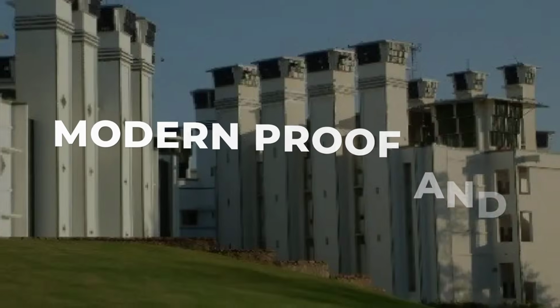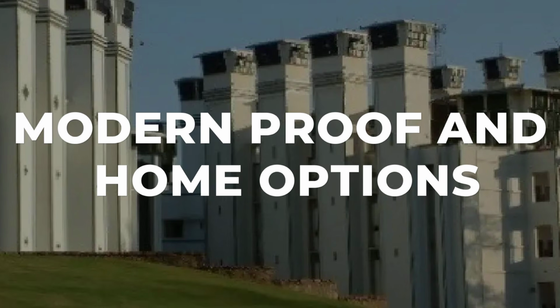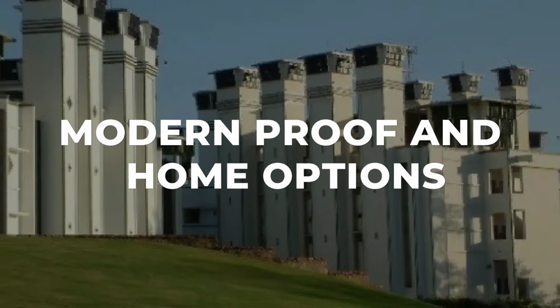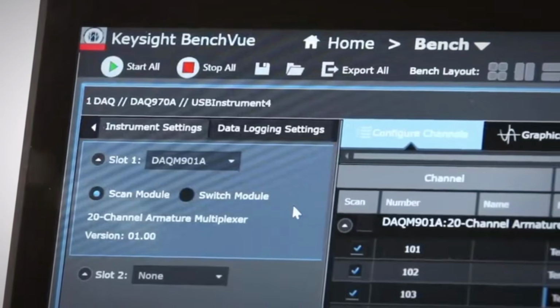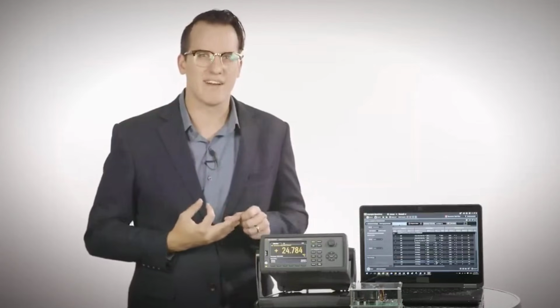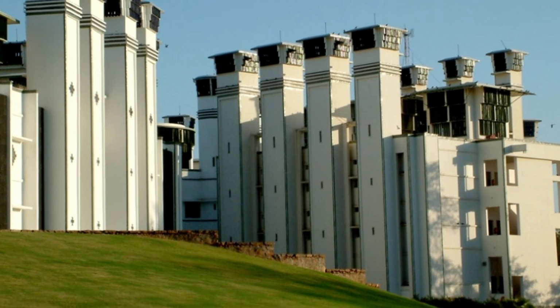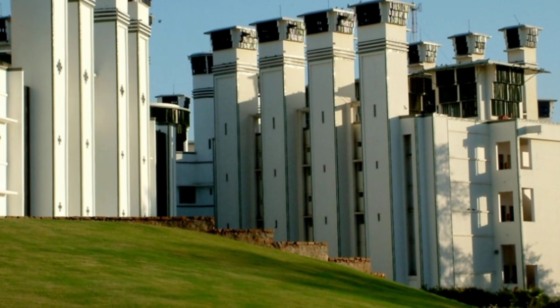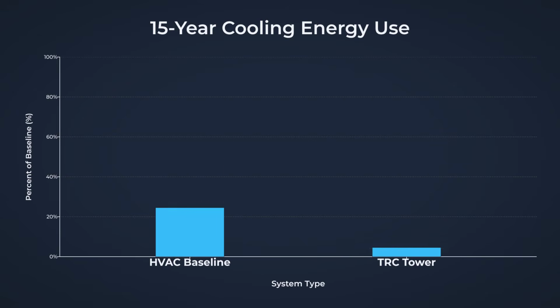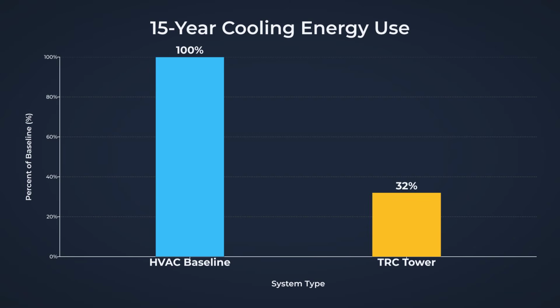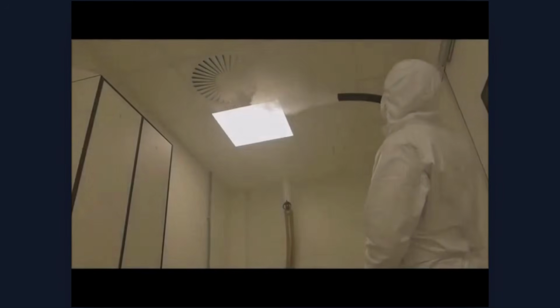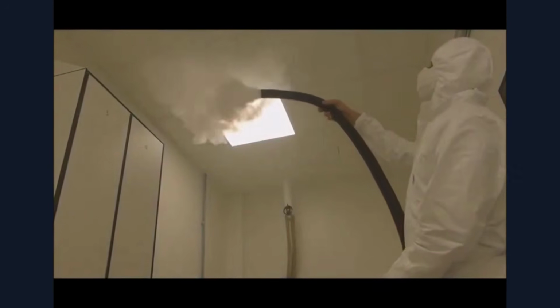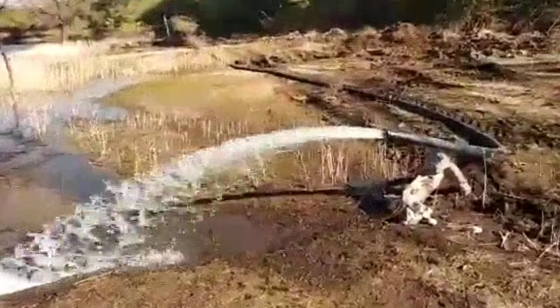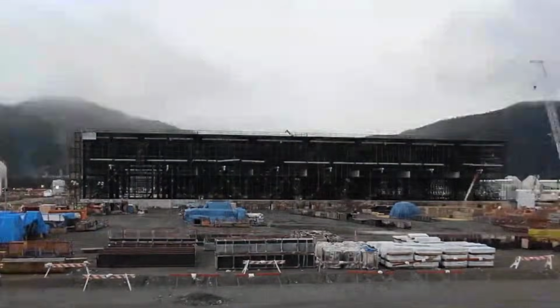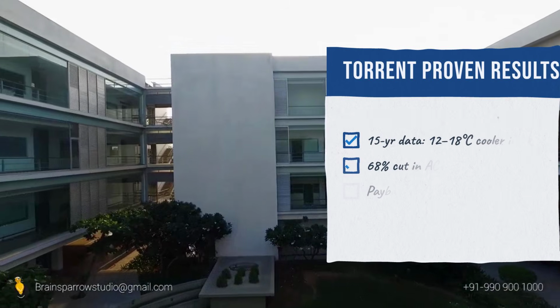At the Torrent Research Center in Ahmedabad, passive downdraft evaporative cooling is not just theory, it is measured, metered, and proven on a scale that mechanical systems struggle to match. Over a 15-year monitoring program, the TRC tower, 20 meters tall, cut electricity use for cooling by 68% compared to a conventional HVAC baseline. The system, which cools a 10,000 square meter facility, relies on nothing more than water, gravity, and solar-powered pumps. The payback period for the extra construction cost, about 7% above a standard roof, was between 5 and 7 years.